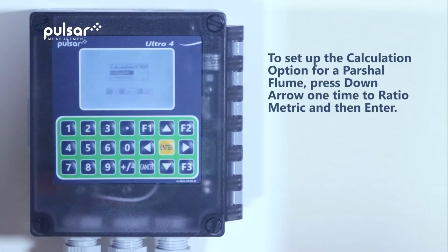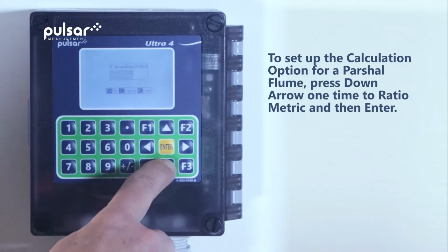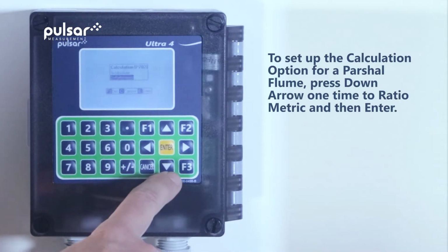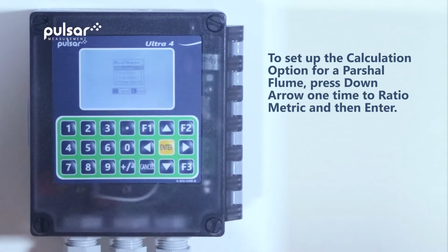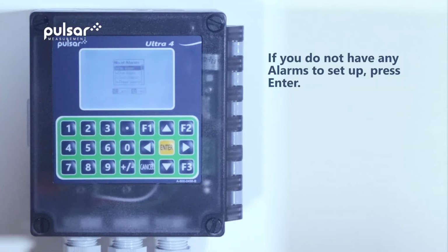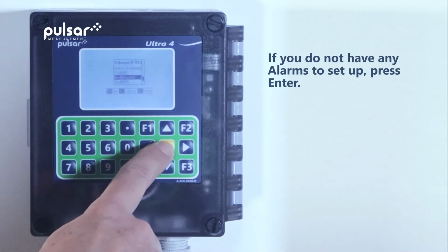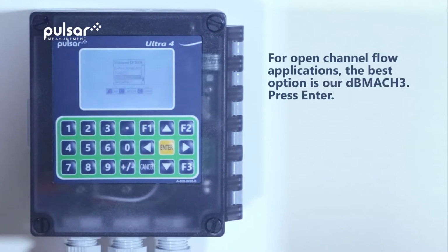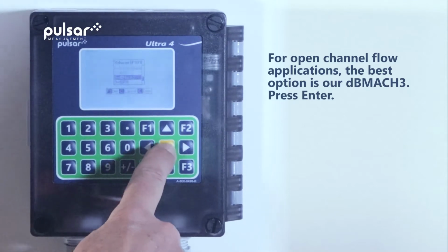Now it's time to set up our calculation option. For a Parshall flume, we want to use ratiometric, so we'll hit the down arrow button 1 time and then enter. We can set up alarms for our Parshall flume, but in this instance we won't, so we'll simply hit enter. For open channel flow applications, the best option is our dB Mach 3. It's currently already highlighted. All we need to do is hit the enter button.